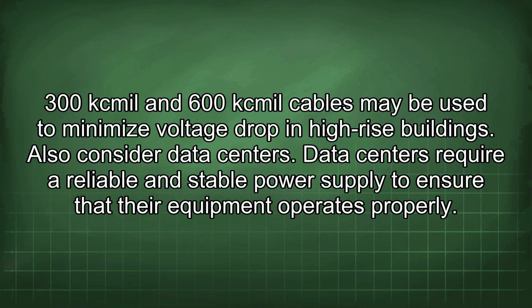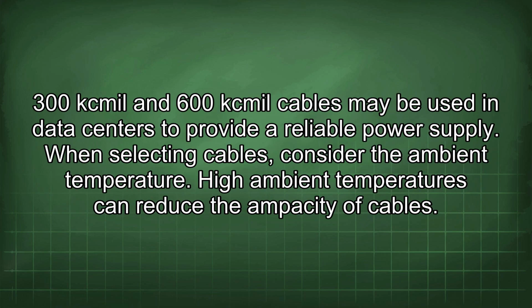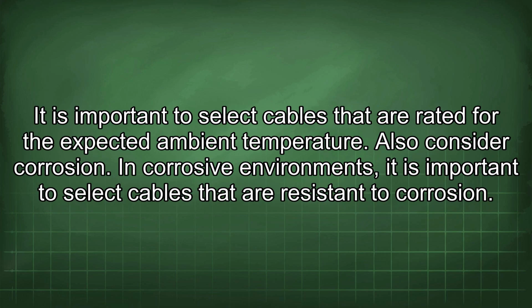Also consider data centers. Data centers require a reliable and stable power supply to ensure that their equipment operates properly. 300kcmil and 600kcmil cables may be used in data centers to provide a reliable power supply. When selecting cables, consider the ambient temperature. High ambient temperatures can reduce the ampacity of cables. It is important to select cables that are rated for the expected ambient temperature.